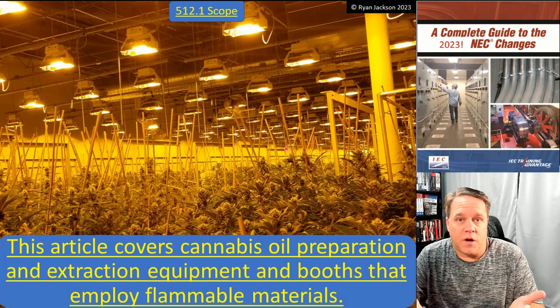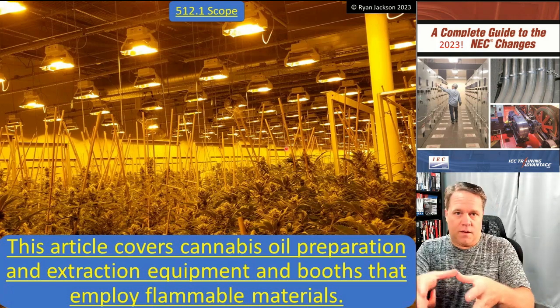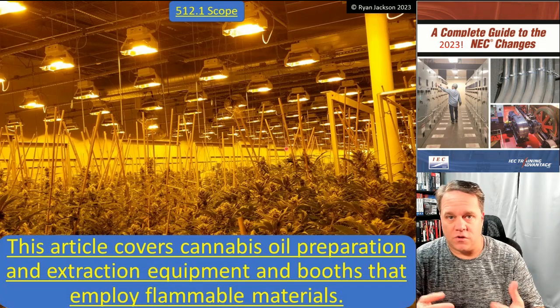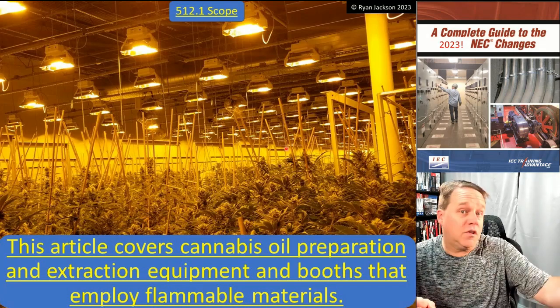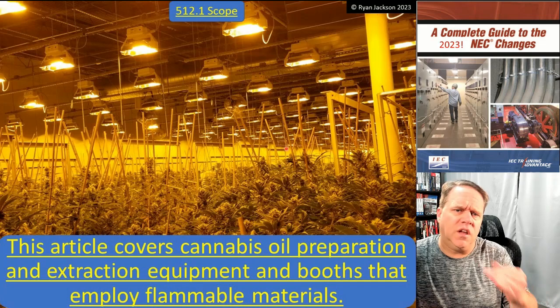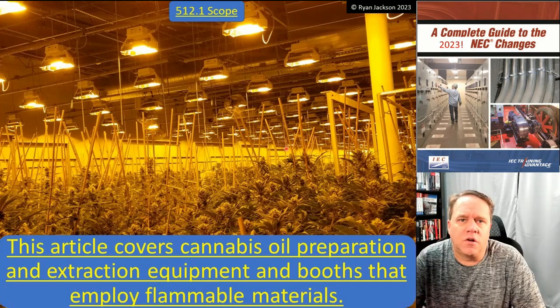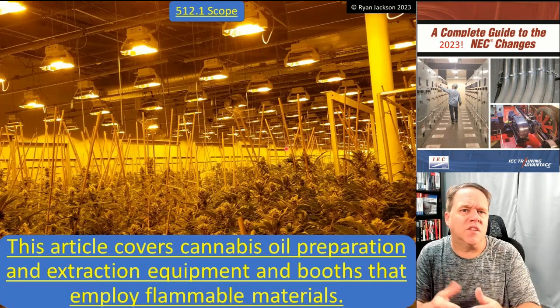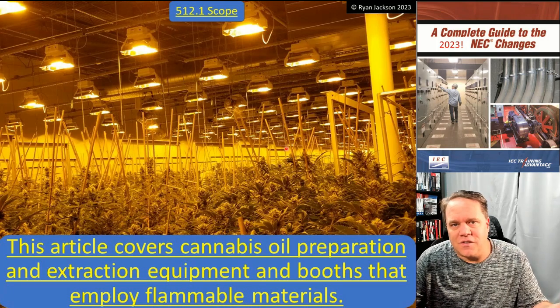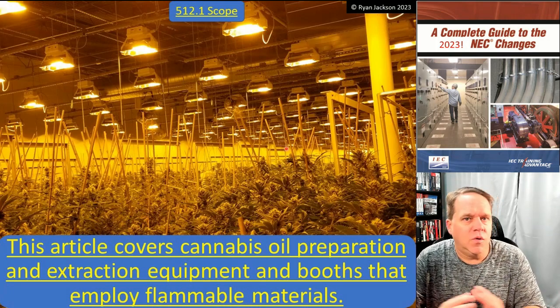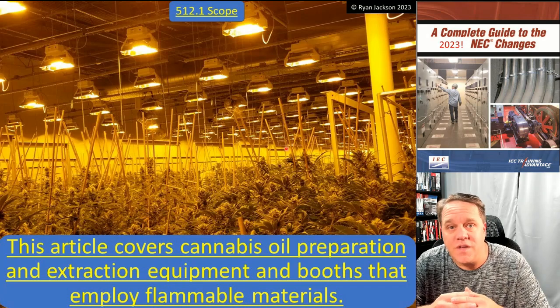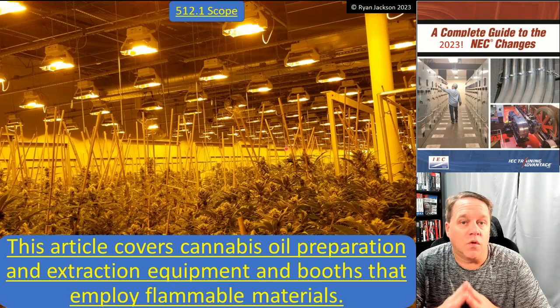You would have an inspector in California saying, okay, well, that means it's going to be classified within 18 inches of the dispenser and 18 inches up. And you might have an inspector in New York saying, well, I don't think it's 18, I think it's 24. You might have an inspector in Chicago that says, I think it's only 6 inches. Look, they're gas stations. We've got them pretty well figured out. We should be able to classify them all the same. That's what we're doing here with Article 512.